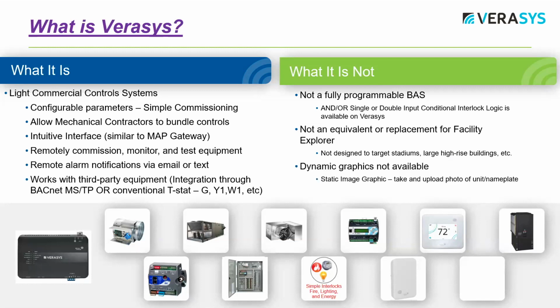There's no dynamic graphics, but you can be very creative with static images. You won't be able to look at a floor plan and see rooms change colors, or click on a room to go to a specific controller. But if you're creative with static pictures, you can give Verasys the look and feel of much larger systems. We're not targeting remote operation centers; we're looking at light commercial applications where owners may or may not even have a footprint in the building itself.